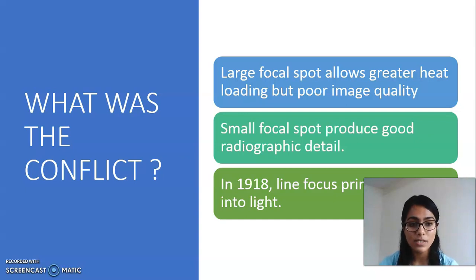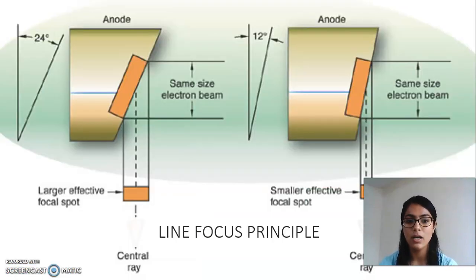So in 1918 line focus principle came into existence. What is line focus principle? What does it say? The focal spot size and shape is determined by the size and shape of an electron stream that is produced by the cathode and bombarded by the anode.